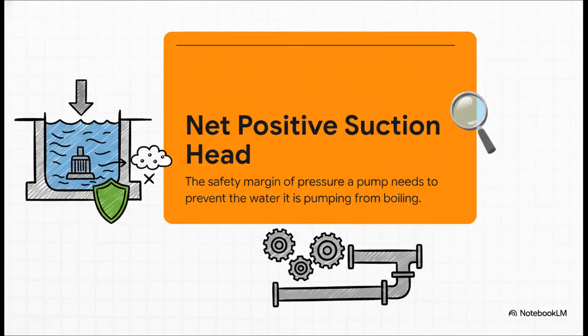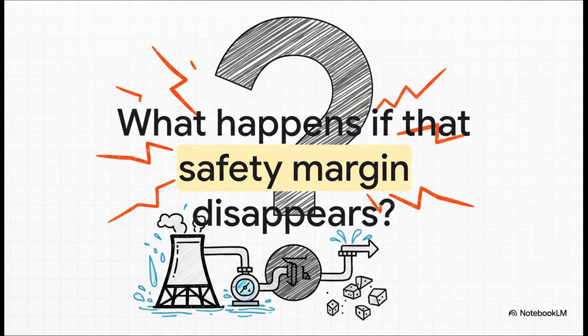So, to get cavitation, we first have to understand this thing called NPSH, or net positive suction head. Let's just simplify that. Think of NPSH as a pressure safety margin. Every single pump needs a certain amount of pressure at its inlet to keep the water it's pumping in a nice, stable, liquid state. So what happens when that pressure drops too low? When that safety margin, maybe because of a bad system design, just completely vanishes?